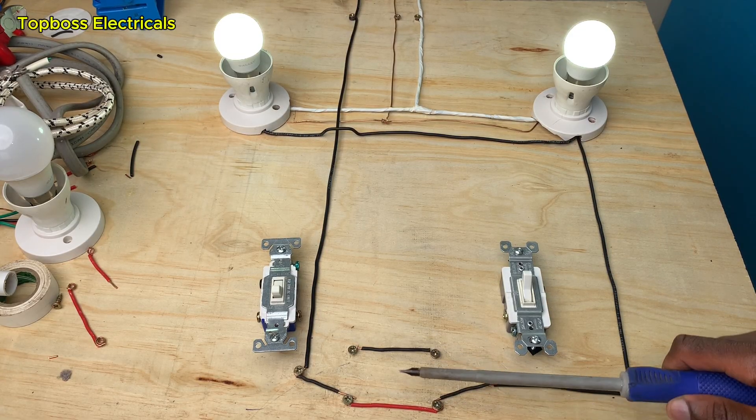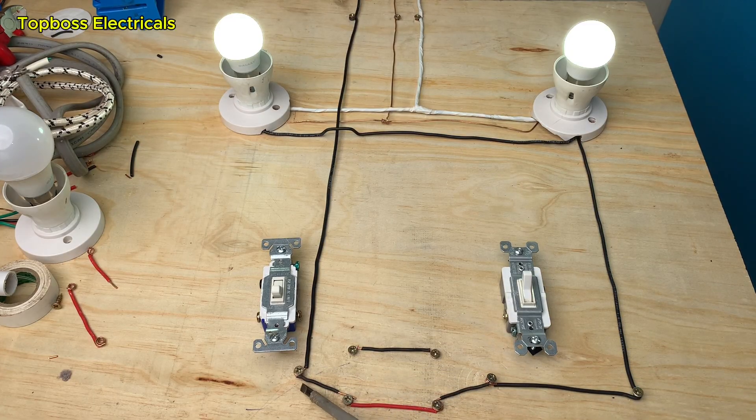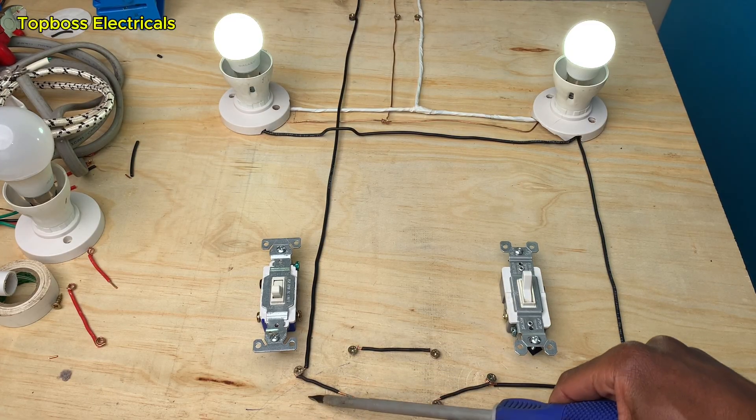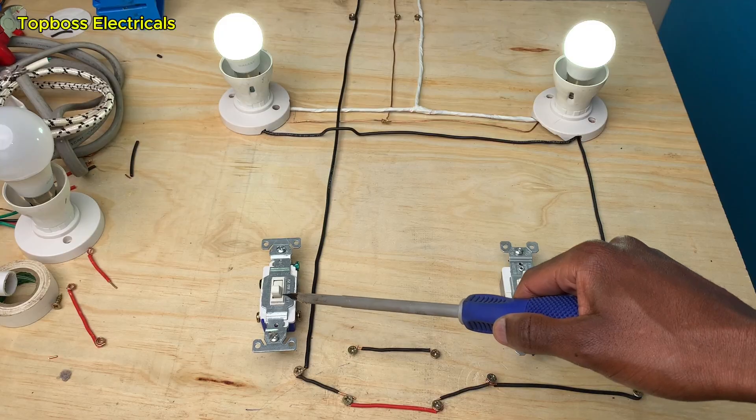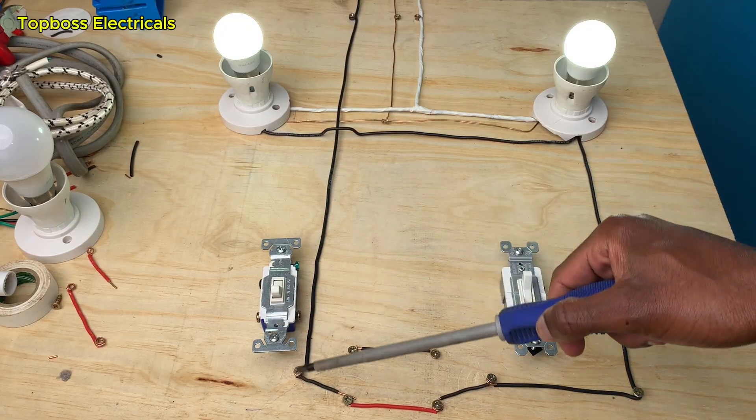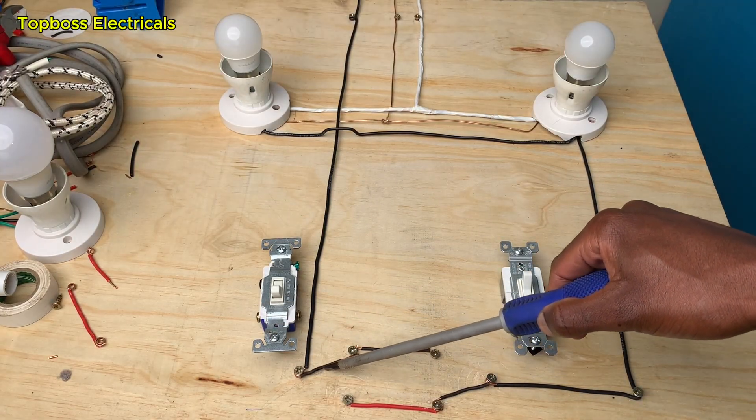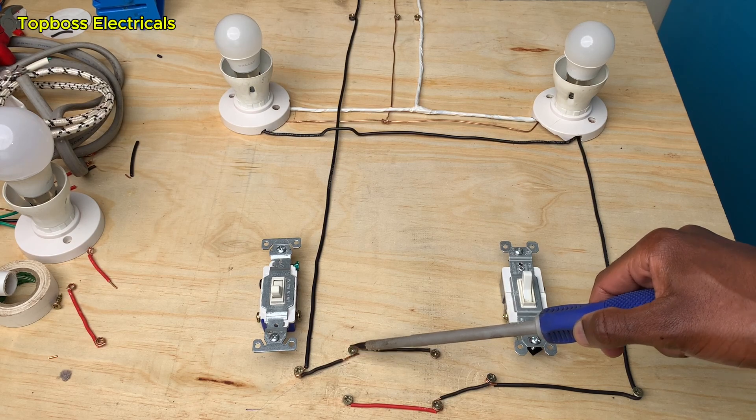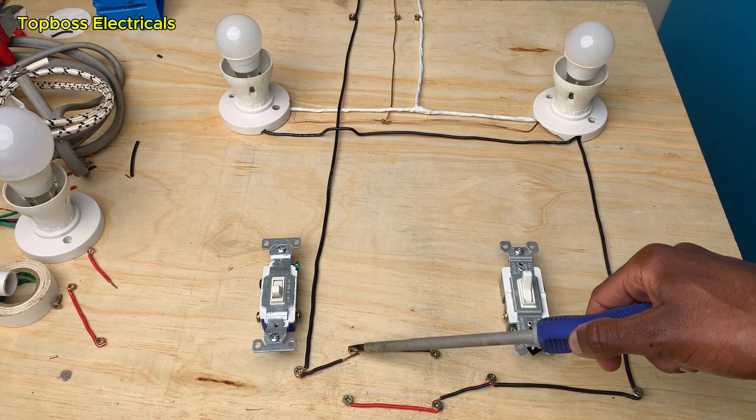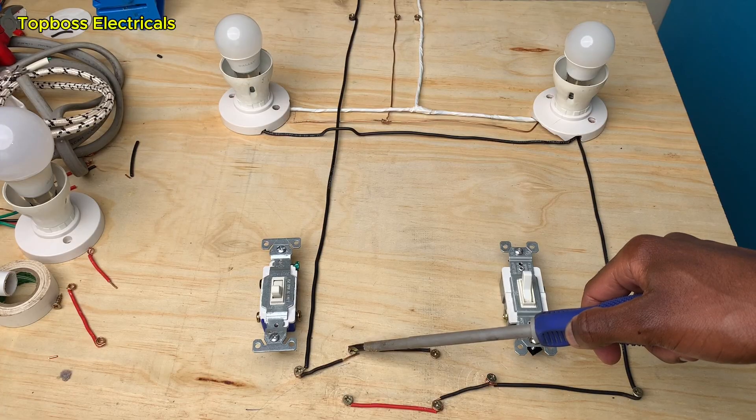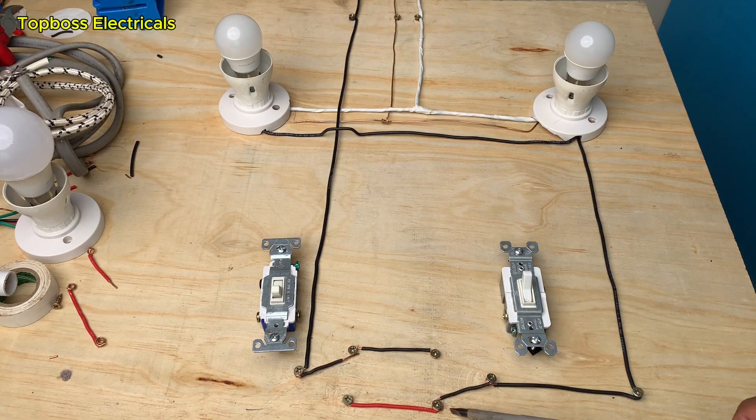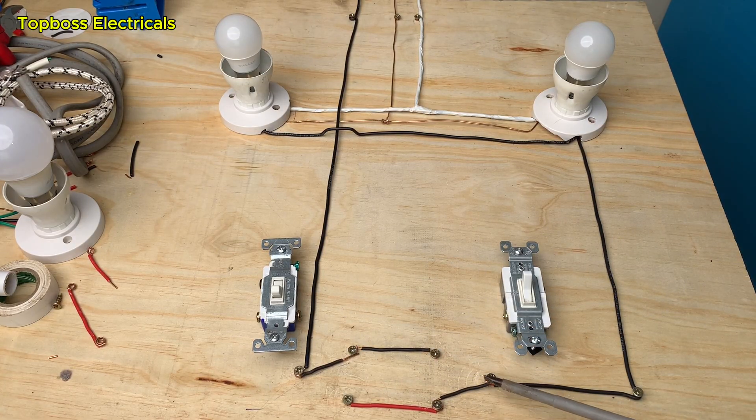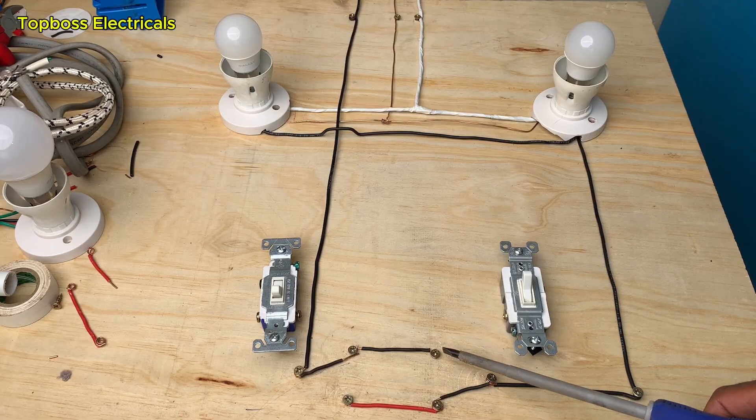If I flip it in any direction, it means that this common is either engaging on this traveler or this traveler. The same happens here: every time that I touch this switch by flipping it up or down, it engages automatically on one of the travelers. It may engage on the upper part to turn it off or on, depending on where this other common is attached to the travelers.